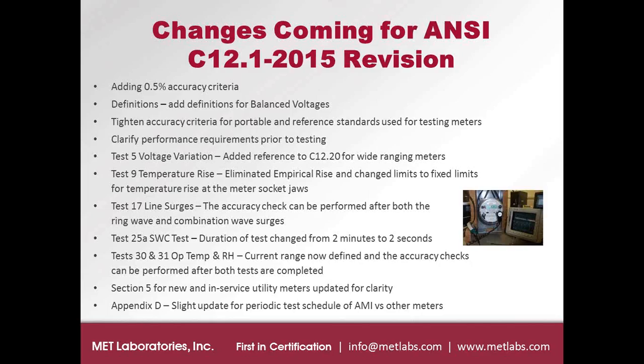Test 17, line surges, they're the ring wave and the combination wave that Monty's group performs. There's been a bit of relaxation in terms of allowing an accuracy check of before and after full load, light load, power factor. Accuracy check to be performed before and after the two of those surge events rather than after each. Just helps quicken the pace along a bit. Test 25A, there was a typo really in the document all along, and it talked about a 2-minute duration for that test, and really it's a 2-second duration, and that harmonizes it with other industry standards.